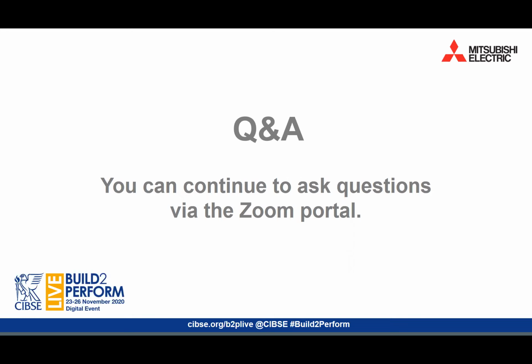Another question from Praveen. What is the maximum capacity of the QAHV that is available? Do you have a 200 kilowatt as a single unit? So we have one size module. It is a 40 kilowatt nominal system, at 7 degree ambient temperature with a 65 degree flow temperature. But you can have up to 16 of those 40 kilowatt modules as a single control unit. That would take you well over the 200 kilowatt that you would need, and they can be packaged quite close together as well. So hopefully, Praveen, that helps to answer that question. Thank you very much.